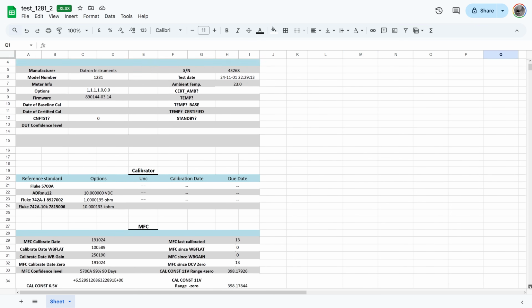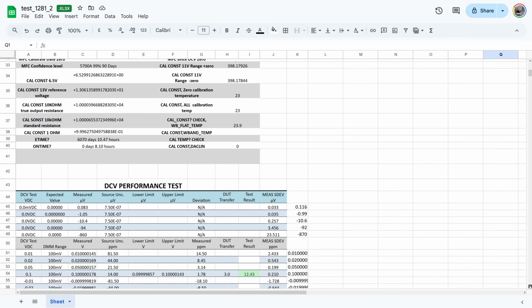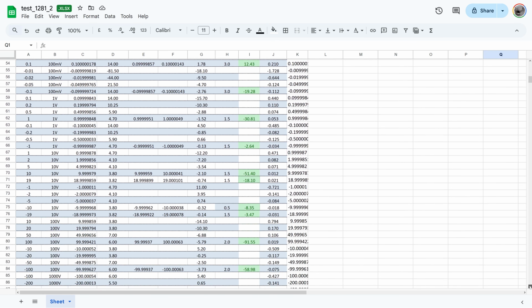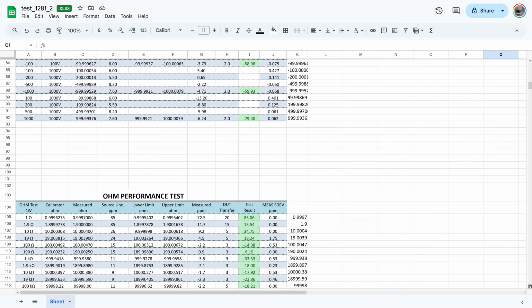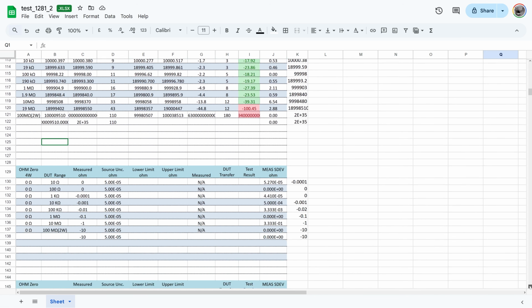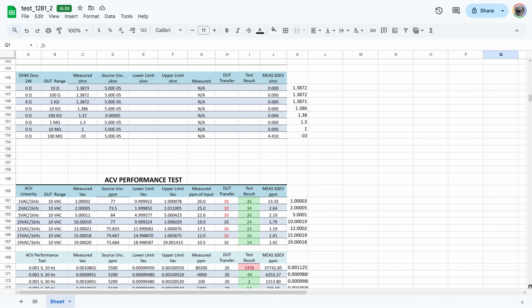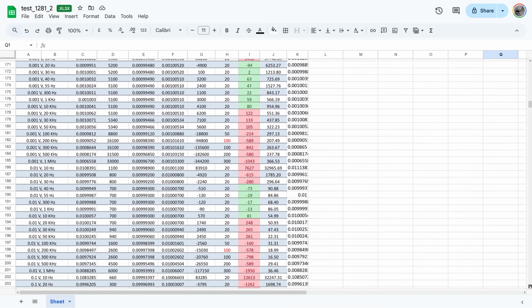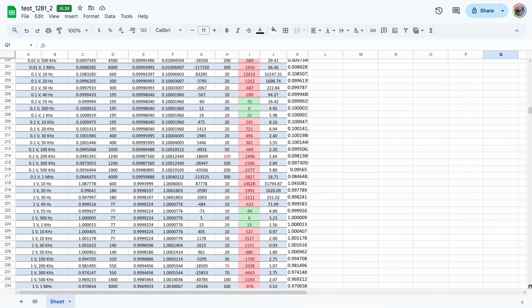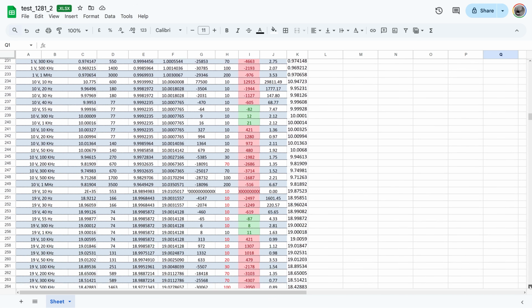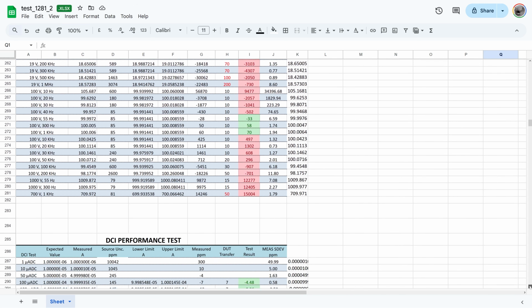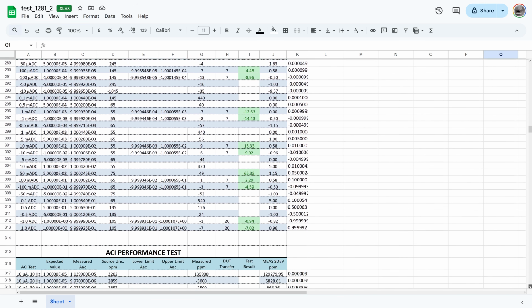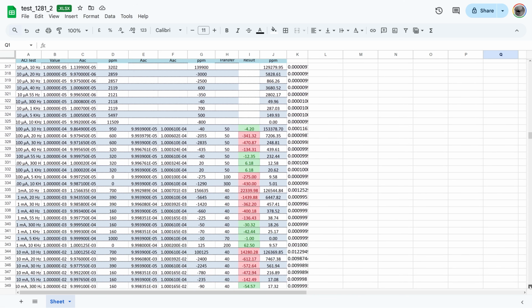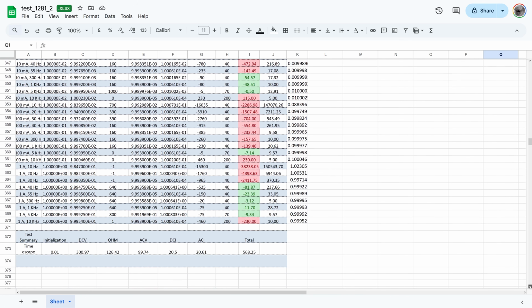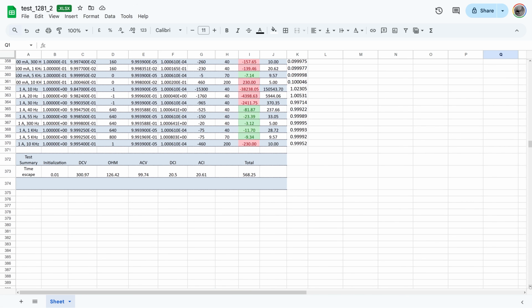I also ran a slightly modified script from the XDev's archives. This was originally meant as an all-round comparison for Model 4950, so the pass-fail limits are not suitable for our DUT today - it's actually a lot looser around the ACV and ACI ranges. So the small red numbers are okay, and what few excessively large red numbers we see can be explained by a settings mismatch, such as a default 100 Hz high-pass filter.